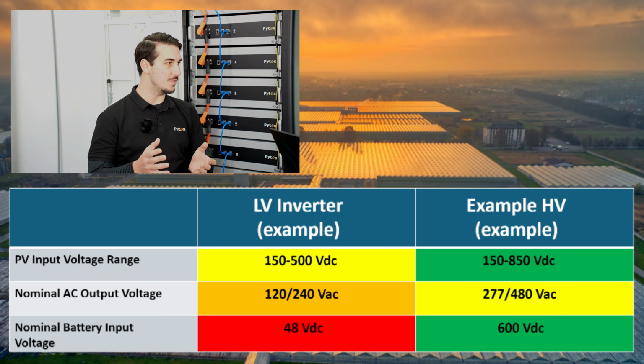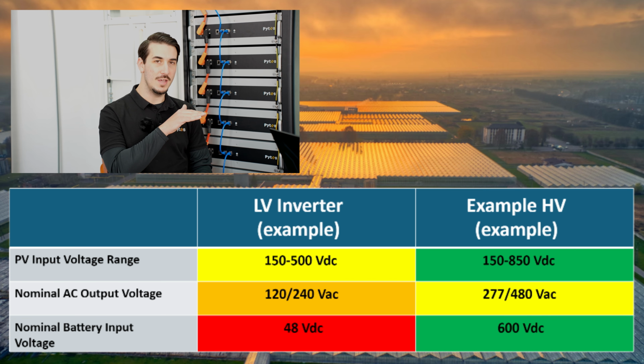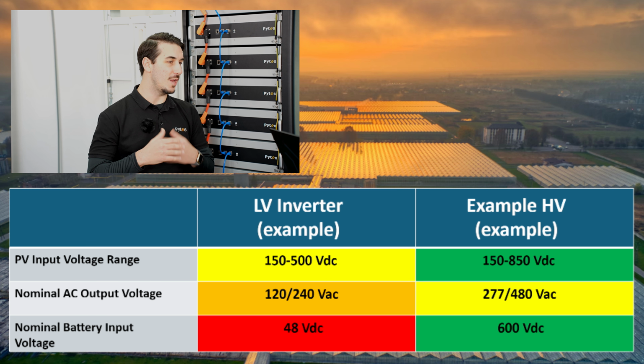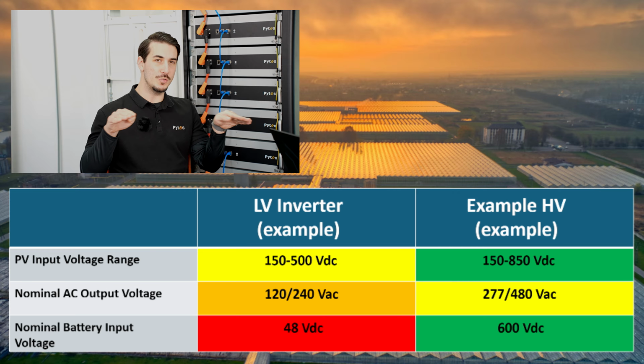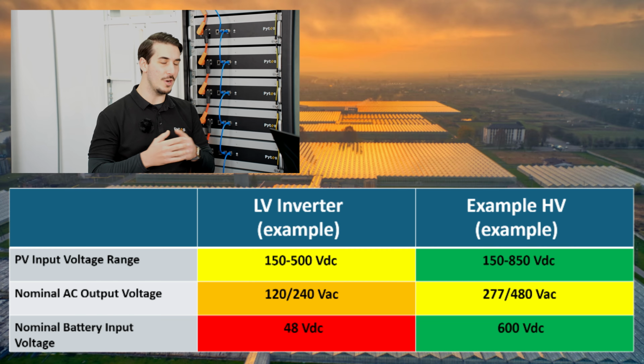One of the biggest advantages for me is that in a high voltage battery system, your voltages from the different inputs are running at a more similar potential. What I mean is the voltage from your solar panels, the voltage of your AC output, and the voltage of the batteries are all a little closer together, compared to a low voltage system where your batteries are down at 48 volts and everything else could be 200, 500, 600 volts. Keeping everything closer together helps reduce conversion losses and generally makes the system operate more efficiently overall.